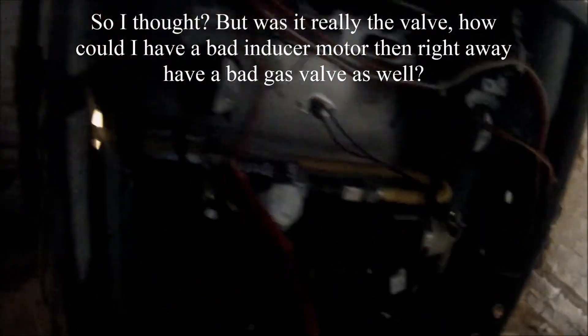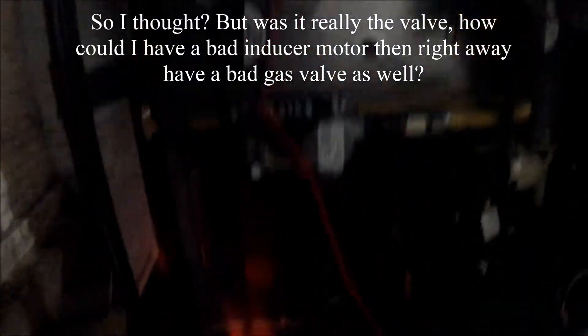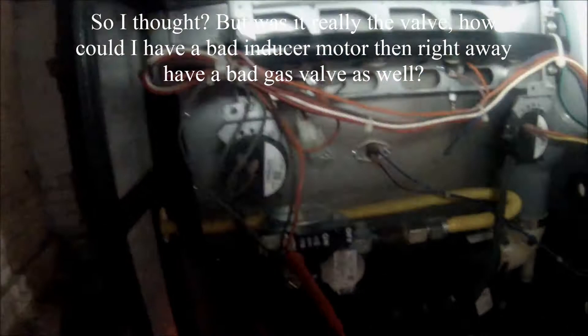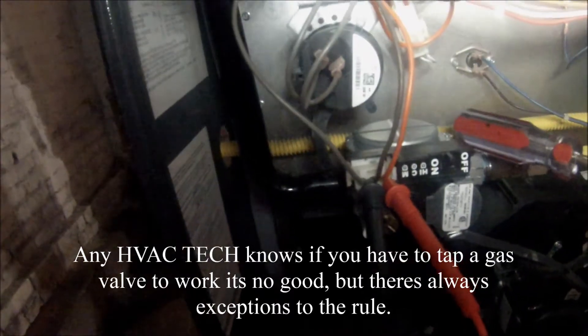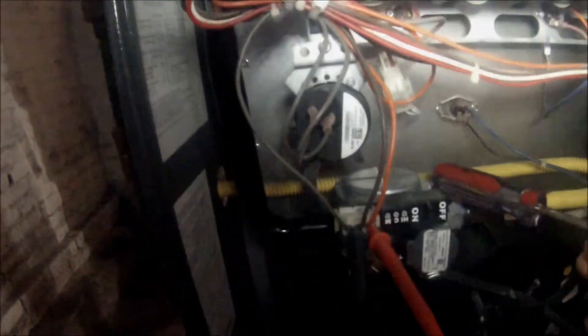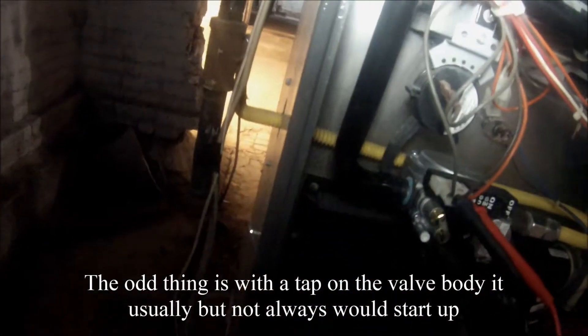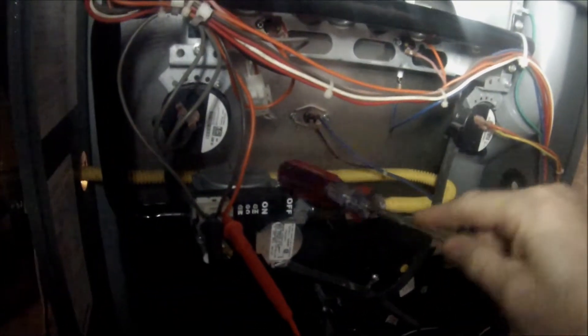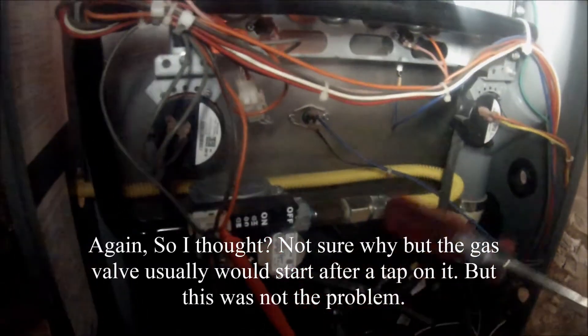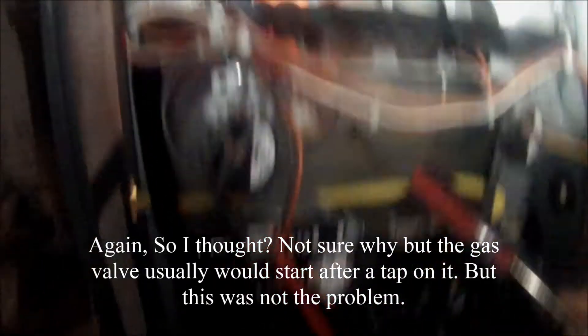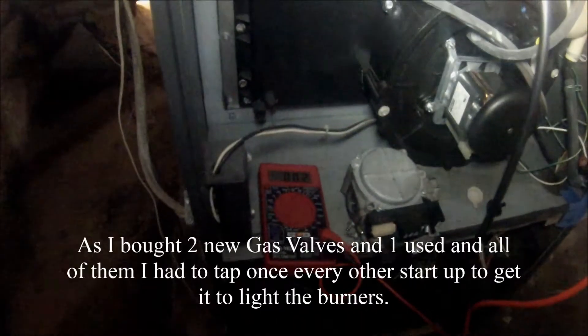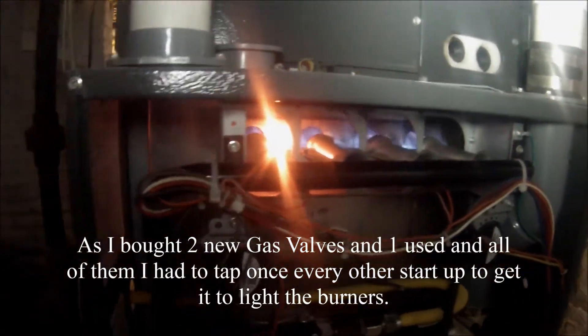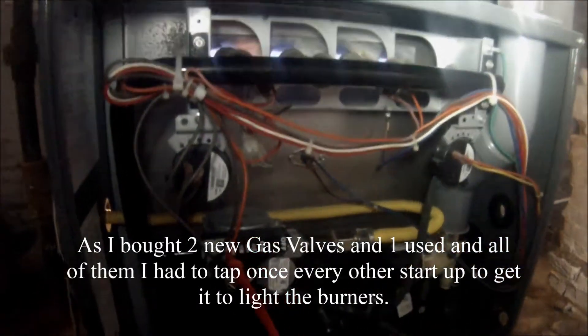So that's a bad valve. And I'll even demonstrate a little love tap on this valve and then it'll start up. Just with the back of the screwdriver, real light. So this is going to shut off. The inducer is going to shut off and it's going to try again. And so this valve has got a sticky, it's stuck. There it goes, it's turning on. There it goes. And that's from barely tapping it there. I mean, that shouldn't, that's a bad valve.